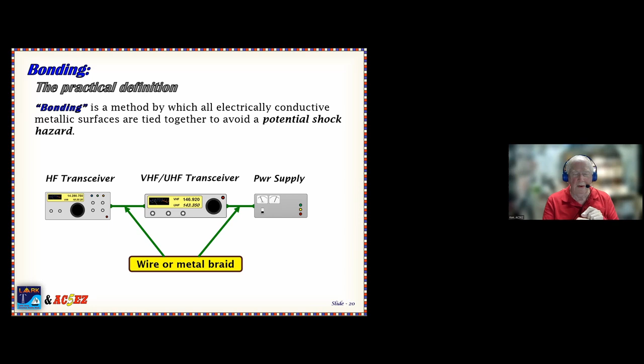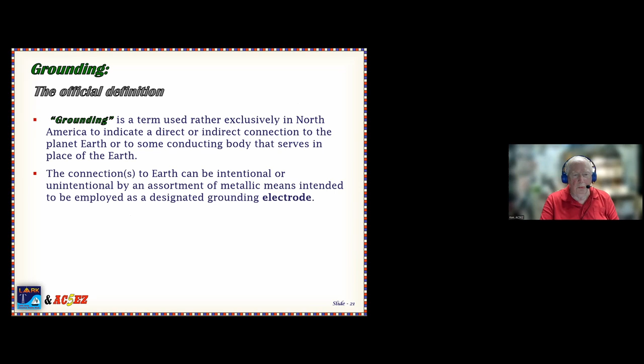Grounding is a term that's used rather loosely in North America. When we say we're going to ground something, that means we're going to attach it to Mother Earth. But if you were to go over to England or to Europe somewhere, they use a term called earthing, E-A-R-T-H-I-N-G, instead of grounding. What it is, it's a way of connecting something to Earth. It can be an intentional connection or an unintentional one by some associated metallic means intended to be employed as a designated grounding electrode. And we know what a grounding electrode is.